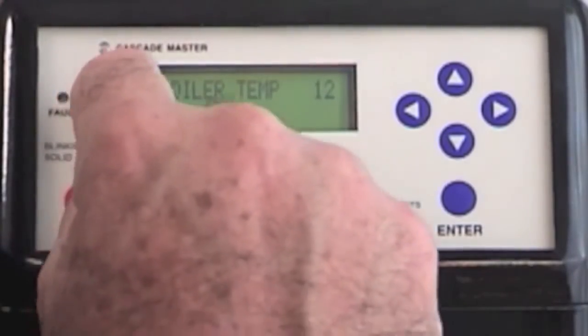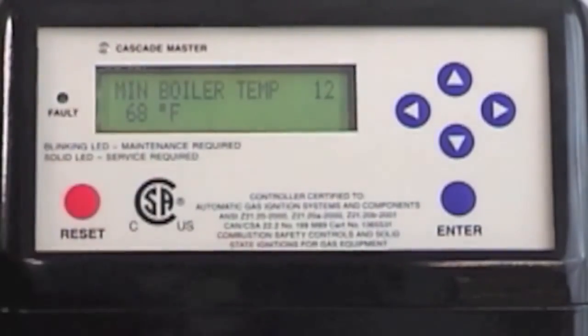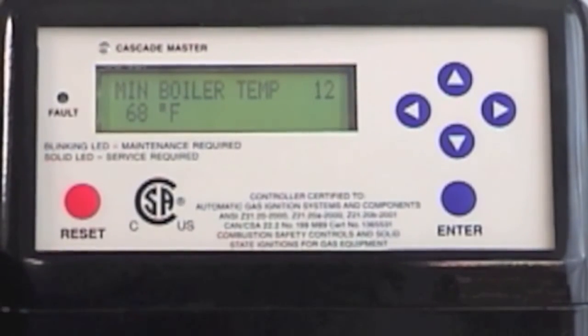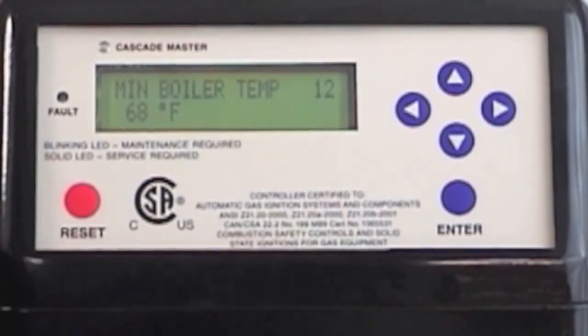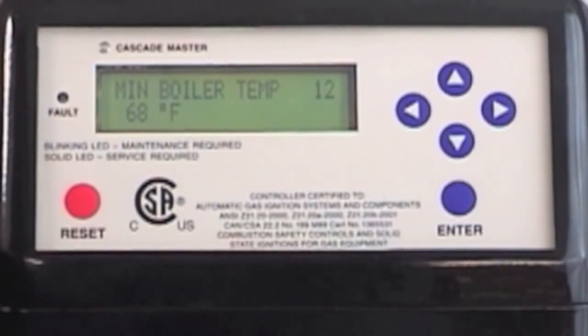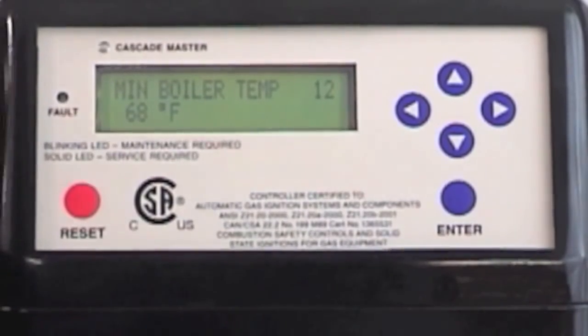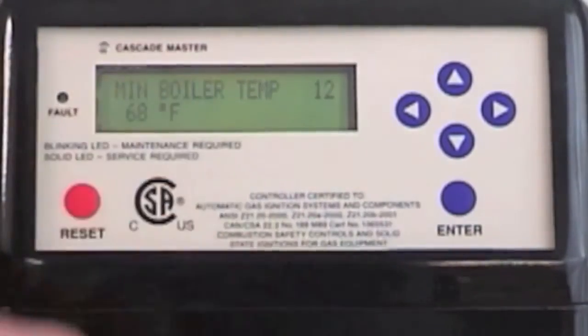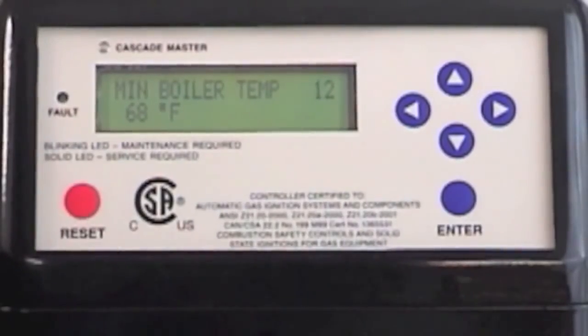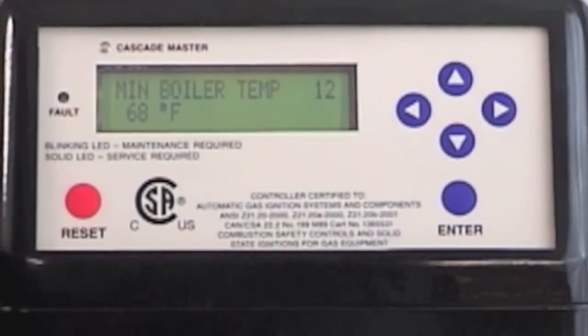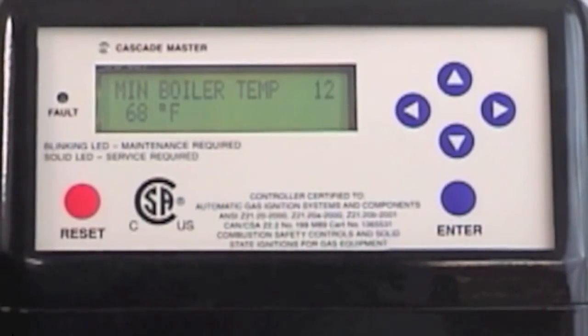The next question is the minimum boiler temperature. If you set an outdoor reset curve and do not choose to use warm weather shutdown, that is a linear line that continues down. You may have a house with tile floors — tile bathroom, tile kitchen — where you want a very low temperature during the summer of water flowing through the floor to prevent condensation and cold feet. Most people with tile floors might run it at 85 degrees during the summer months. This is a condensing boiler, and it does not cause an issue.